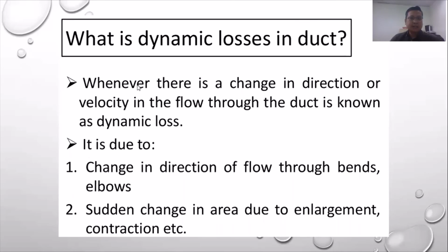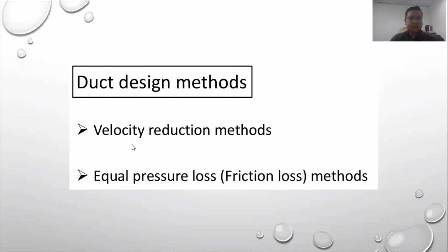And dynamic losses in duct, how to measure the losses: bend, elbow, sudden change, and so on. And the duct design method is based on two types, velocity reduction and equal pressure loss. So when we design the duct, we measure the velocity of the air supply and also the pressure. This is enough to supply to the certain area. So we design based on this.